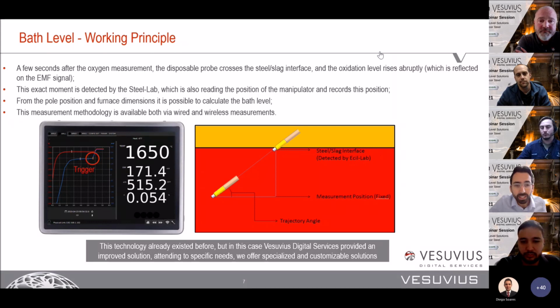For those familiar with oxygen measurement, on the left side you may recognize this as an instrument for acquiring and showing an oxygen measurement. The red line is the temperature, and the blue line is the oxygen. When a disposable probe is immersed into the steel, you have a period of stabilization - you see the traces going up. The temperature goes up, and the oxygen cell, which is the main part that detects oxygen, also gets thermally stable.